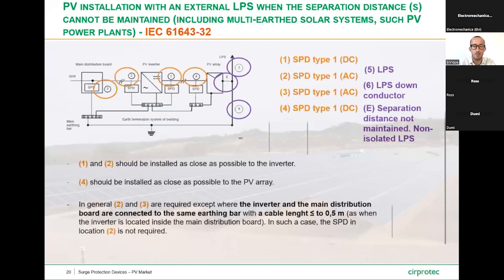In that scenario, it's required to install an SPD in the location 1 in the DC side close to the PV inverter, which should be a type 1. Also in the location 2 in the AC side of the inverter, an SPD type 1. The same in the location 3, close to the distribution board, should be installed an SPD type 1. And the last one in the location 4, close to the PV array in the DC side of the PV installation, an SPD type 1.